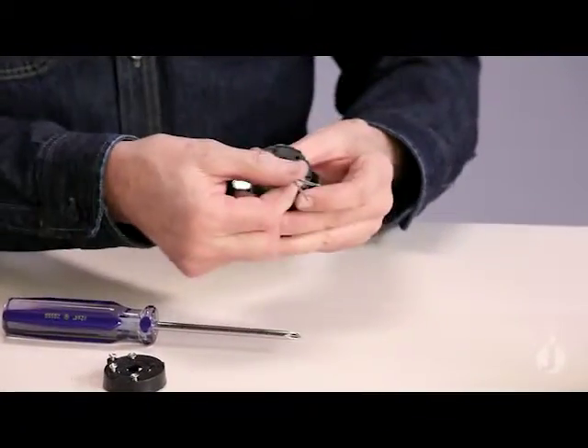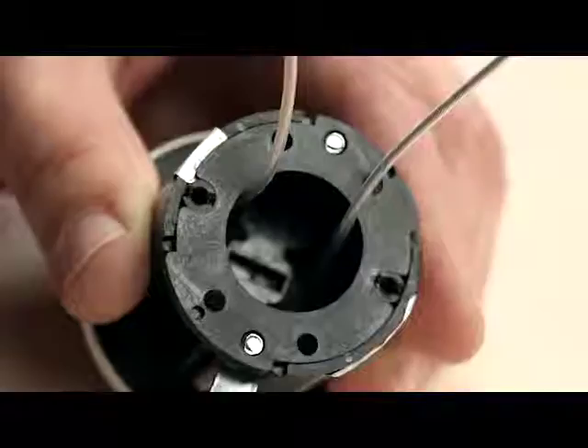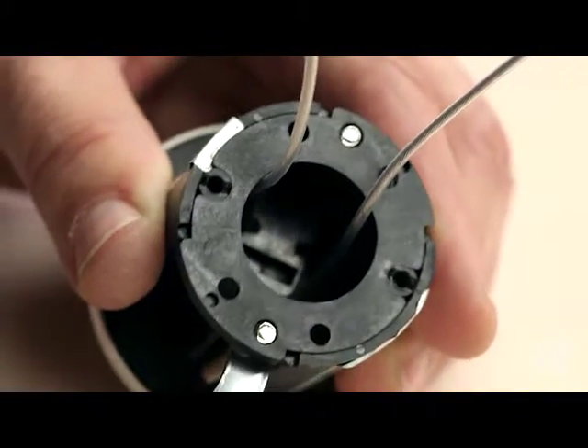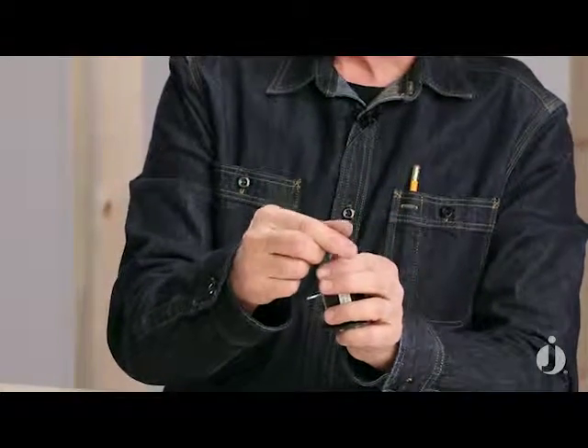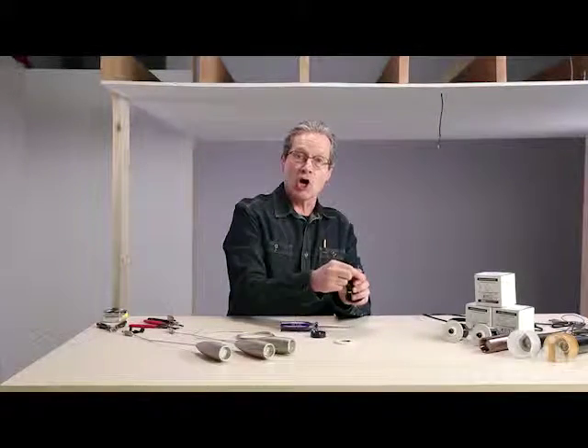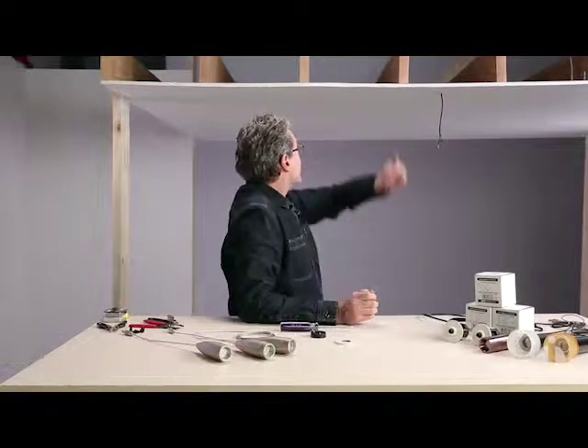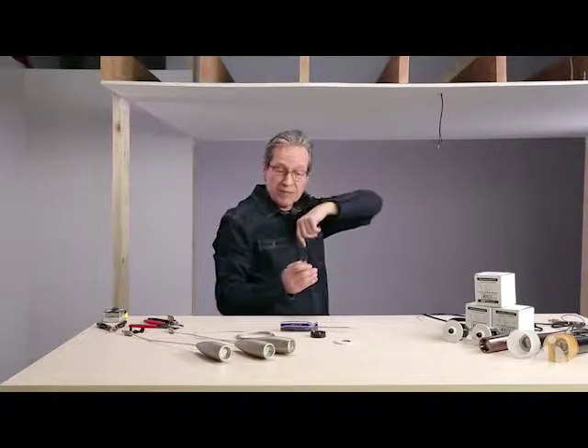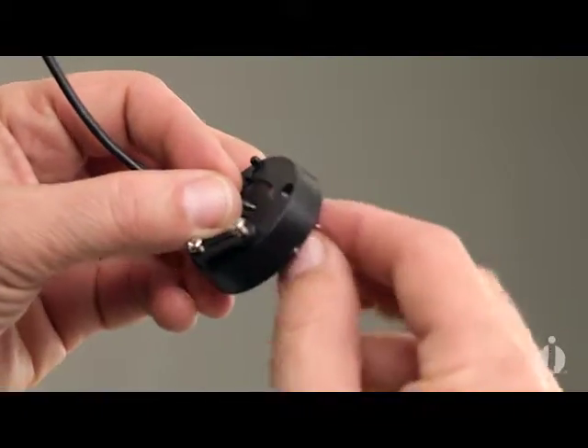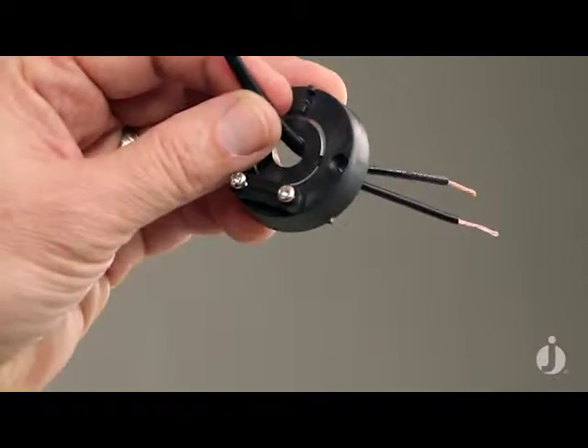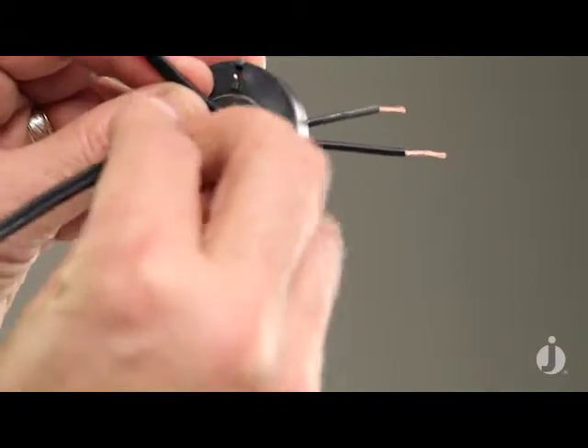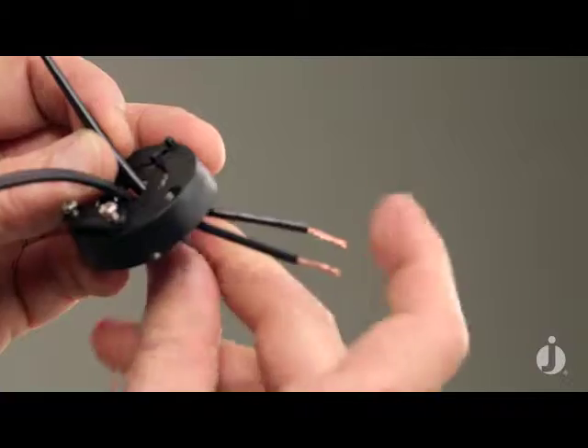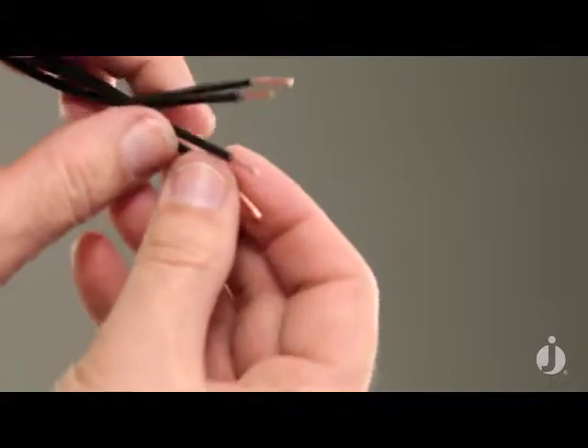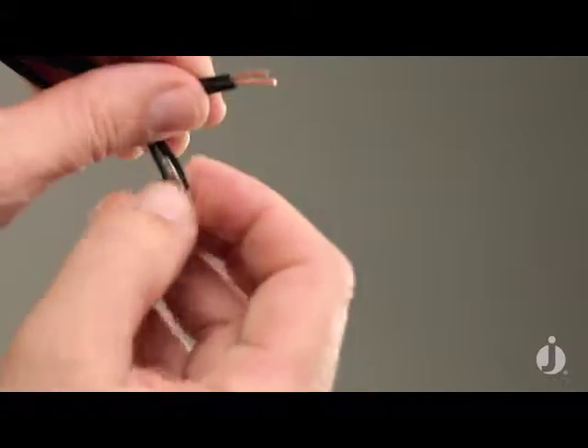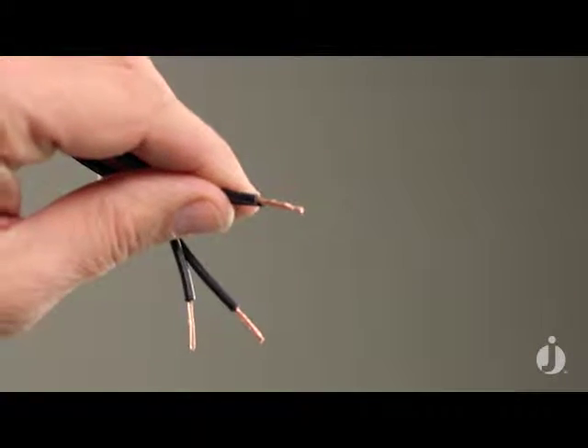And I have a space in there. So this compartment will house the junction of the two wires from the fixture, the wire leads from my transformer, and the wire leads that go to the adjacent fixture, which will then be fed through my second hole. So let's begin. Since the cover goes on last, I'm going to have to put two sets of wires through there. And one of the nice things about low voltage is that there is no polarity requirements on the 12-volt side. So I'll just be attaching a lead from each wire to one of each of these leads.